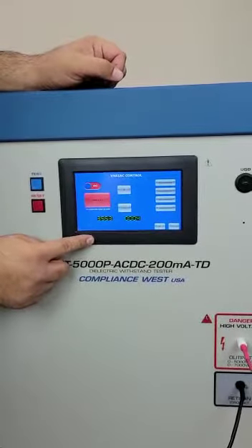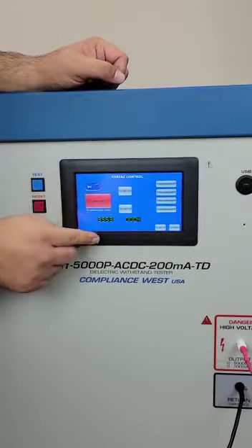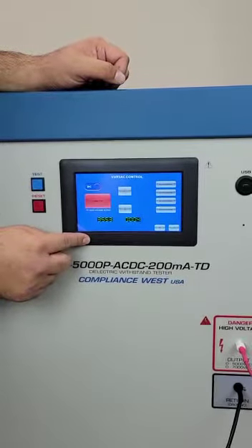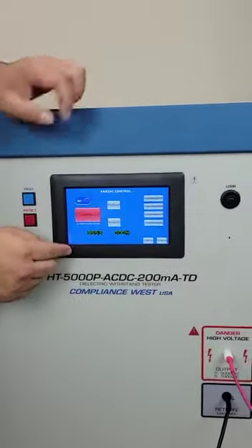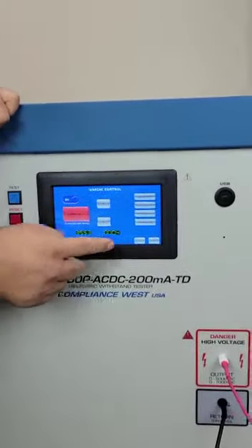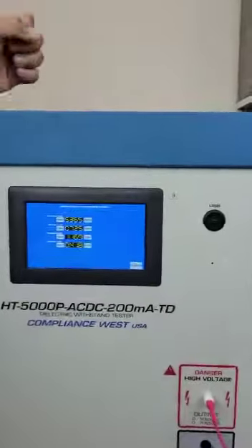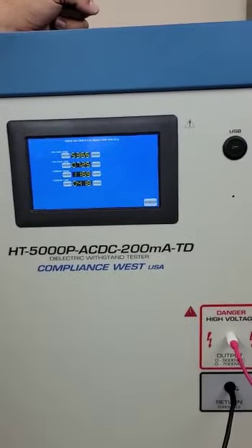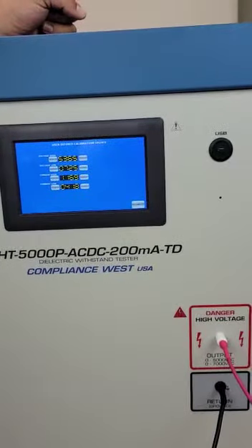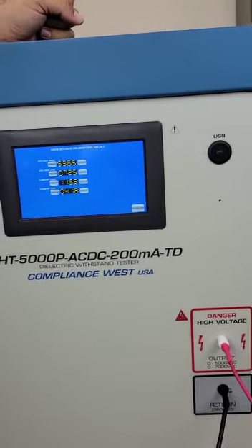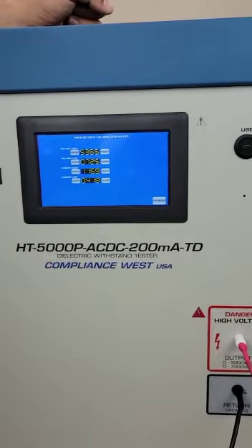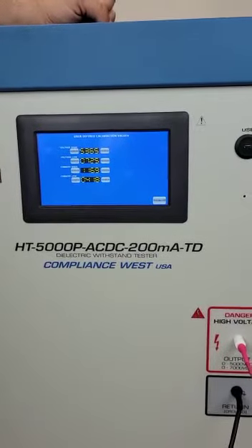To do the DC, we just flip the switch to DC, and we repeat the process. We can show you our values of the DC. You can see it's a little bit higher, since on DC we can reach up to 7,000 volts. For the higher calibration point, we can use something around 5,500 volts. In our case, it was 5,365. And for the lower calibration point, something around the 700.